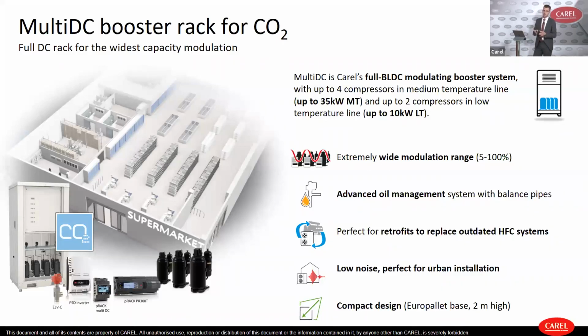So you can put it inside the store with a remote gas cooler or outside the store, according to the needs and the space that you have available in the supermarket and around the supermarket. Again, just to give you an idea of the products that we can provide for this solution, there are electronic expansion valves for transcritical valve management, drivers, controllers, and the Toshiba CO2 compressor, which are available, of course, for the multi-DC booster rack, but also for the EQ solution that I was speaking about before.